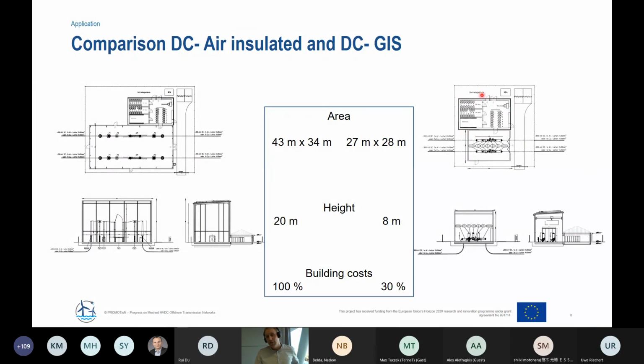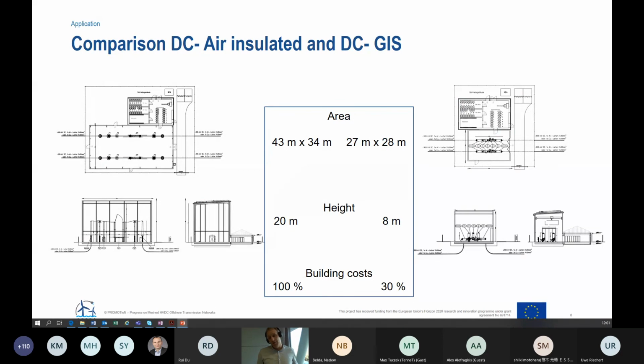It's more or less the secondary part of the control system and protection system, which determines the size of the substation, which is mentioned here. So, some values which you see here. The area which is needed is 43 meters by 34 meters. Could you reduce it to 27 meters by 28 meters? Maybe it's more determined by the secondary systems. And the height, maybe it was 20 meters before, and now it's only 8 meters, which results in the building costs, which I consider only the building costs, which are now 100% here on the AIS side. Could you reduce by up to 30% at the DC side, which makes a lot of savings.